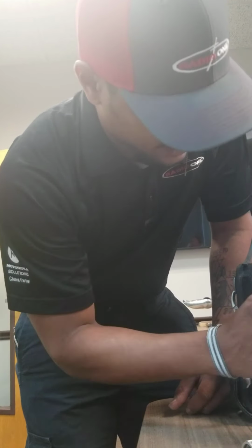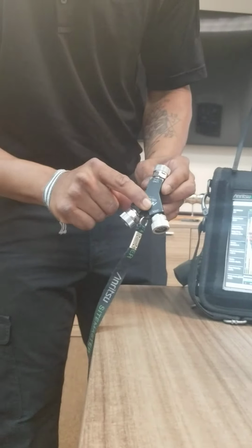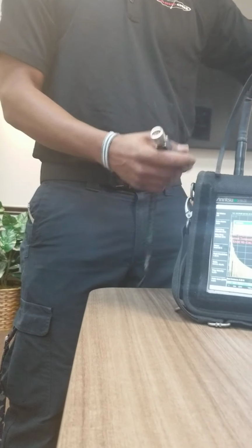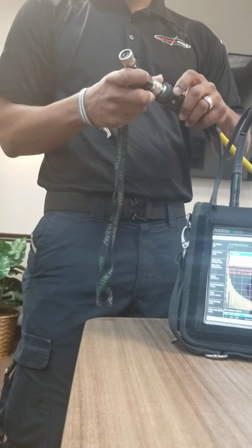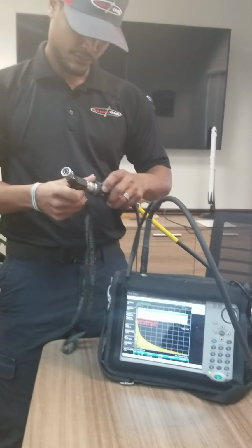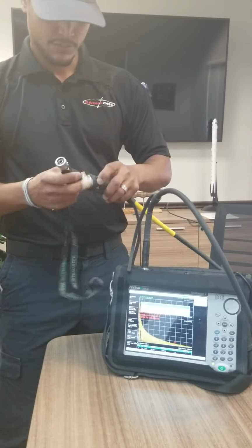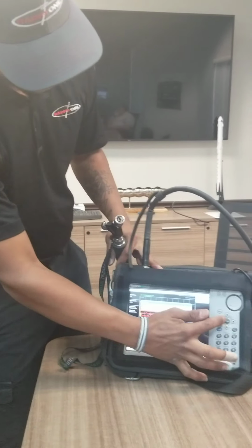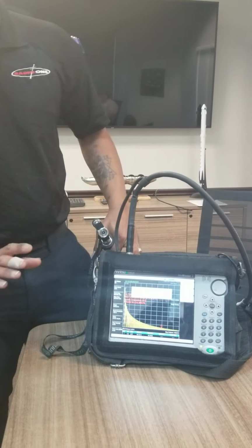So let me give you an example right now. I'm going to do a start calibration. The machine is going to tell you which port of the load you're going to put first, always. So it says continue, open to install module to RF out port, which is this one, RF out, and then press enter. So open, see open right here. Go to open, and then you press enter. Boom. You wait.